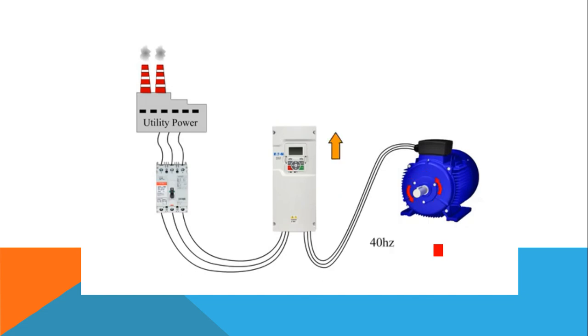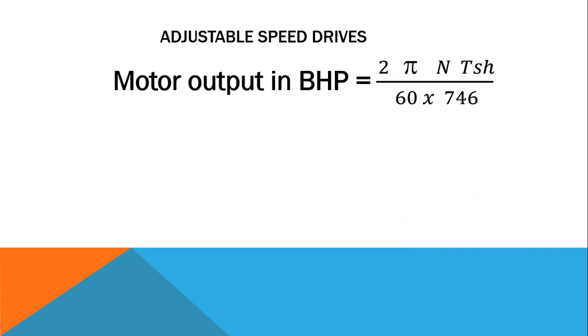If you increase the frequency to 40 Hz, the speed will be between that of 60 Hz and 20 Hz. Actually, it is continuously variable from 0 Hz up to the rated frequency of 60 Hz - the frequency and speed are both varied continuously and smoothly. Now the question is whether only frequency needs to be varied. This is known as an adjustable speed drive or variable frequency drive. The fundamental equation of brake horsepower is: BHP = 2π × N × T_sh ÷ (60 × 746), where N is speed in RPM and T_sh is shaft torque.